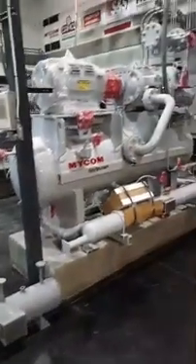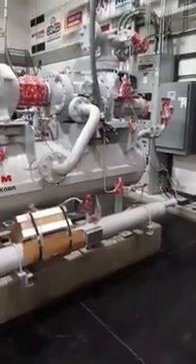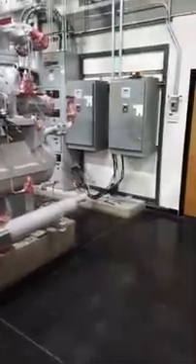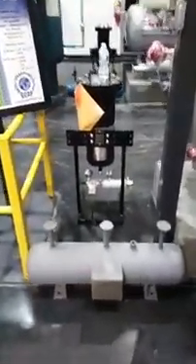We had a lot happen yesterday and I want to give you a showing of what's happening to System A — and at the end of this, you'll have an opportunity to win a sweet GCAT hat. This machine right here is the new high-stage compressor for System A. It's 75 horsepower — big, big machine — with an oversized oil separator for better oil separation, slide valve and slide stop. On the wall over there you can see RAM starters and VFDs; the one on the right will be working for this high-stage machine. We'll be adding an additional USPI oil filtration system on it.